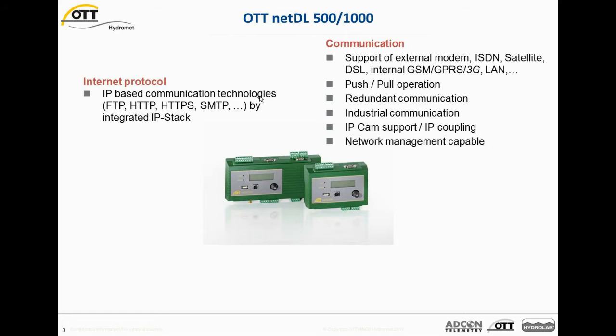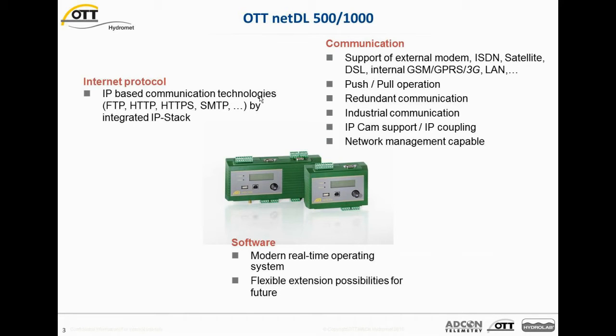We have a lot of communication possibilities with these kinds of Data Loggers. We support external modem, ISDN, satellite communication, DSL. There is an optional internal GSM GPRS modem, the 3G modem is in preparation at the moment, as well as we do have alarm connection possibility. It's possible to run different operation modes like push and pull. Redundant communication paths can be established for highest data availability. In special applications, industrial communication interfaces are available like PROFINET or MODBUS. And the Data Logger supports IP cameras as well as IP coupling, which means the connection of various Data Loggers together via IP. And the Data Loggers are capable to be network managed from a central location. The software in the Data Logger is a modern real-time operating system and it offers flexible extension possibilities for the future.